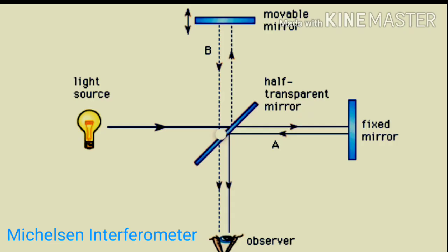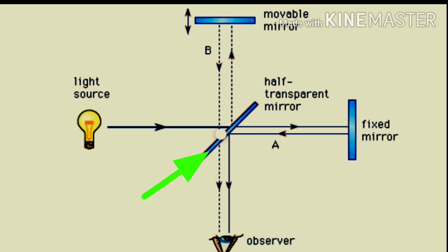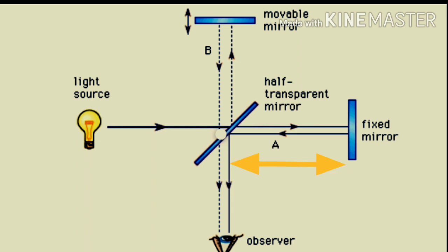This is a Michelson interferometer. Rays from the light source come towards the beam splitter. From the beam splitter, some rays transfer towards the fixed mirror and some are reflected towards the movable mirror. When they come back towards the beam splitter, the rays travel equal path distance from both the fixed mirror and the movable mirror, as shown in the presentation. This equal time and equal distance produces constructive interference.